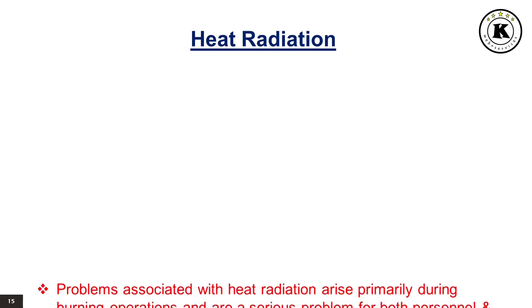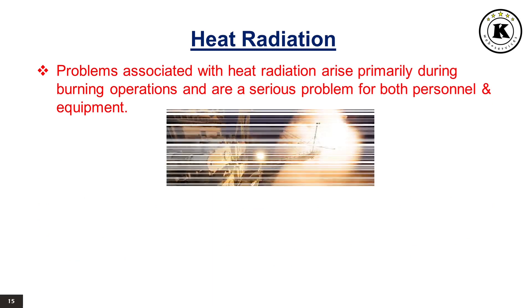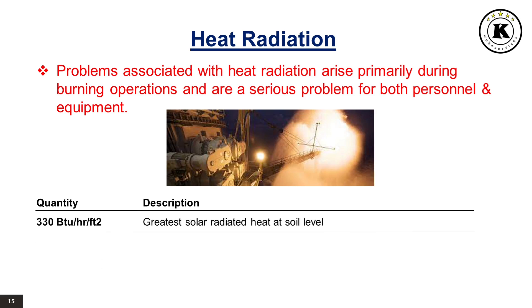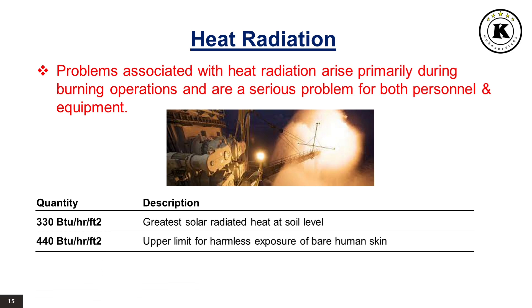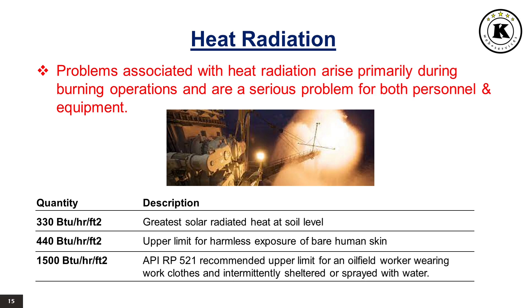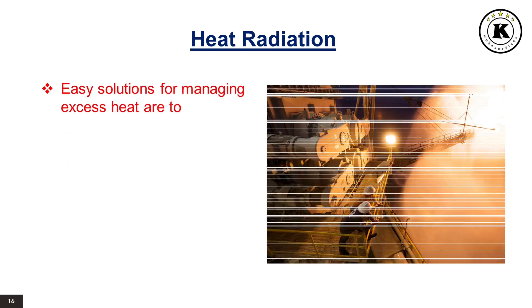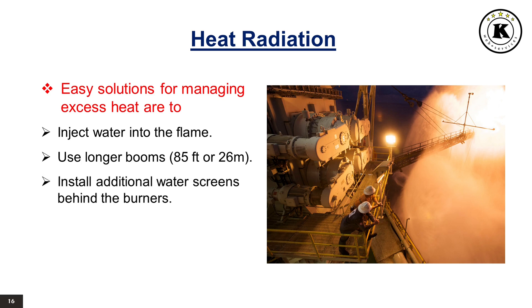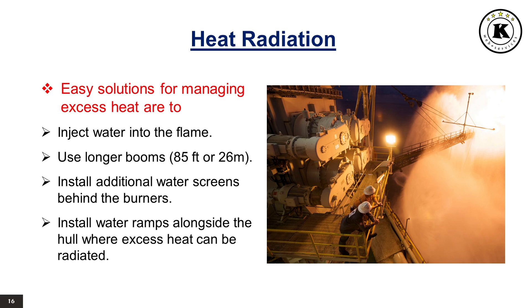Heat radiation: Problems associated with heat radiation arise primarily during burning operations and are a serious problem for both personnel and equipment. 330 BTU/hr/ft² is the greatest solar-radiated heat at soil level. 440 BTU/hr/ft² is the upper limit for harmless exposure of bare human skin. 1500 BTU/hr/ft² is the API RP521 recommended upper limit for an oilfield worker wearing work clothes and intermittently sheltered or sprayed with water. Solutions include injecting water into the flame, using longer booms (85 feet or 26 meters), installing additional water screens behind the burners, and installing water ramps alongside the hull.